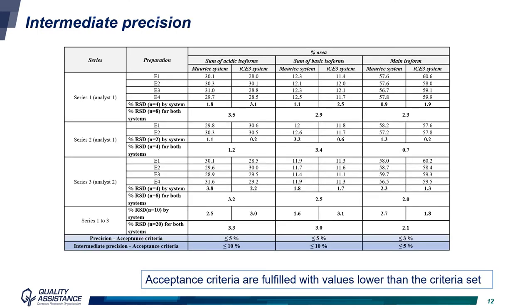Going further, we had in total three series of analyses where samples were prepared by two analysts. For each series, repeatability is lower than the 5% criteria for acidic and basic variants and lower than the 3% criteria for the main variants — both when taking each system individually and when combining data from both systems. Intermediate precision was calculated based on these three series. Criteria were set below 10% for acidic and basic variants and below 5% for the main variants. These criteria are met for each system individually — taking into account 10 values — and also when combining data from both systems (20 values), indicating that the methods are equivalent.